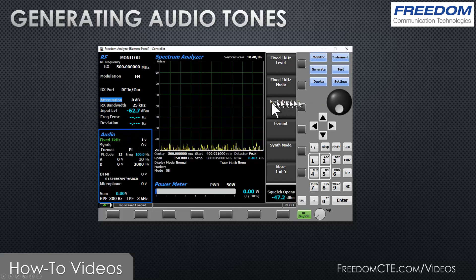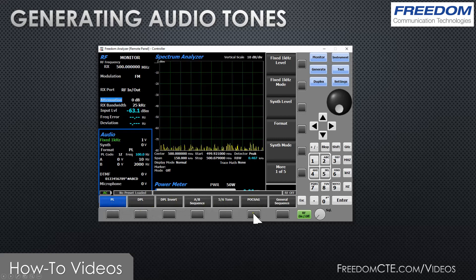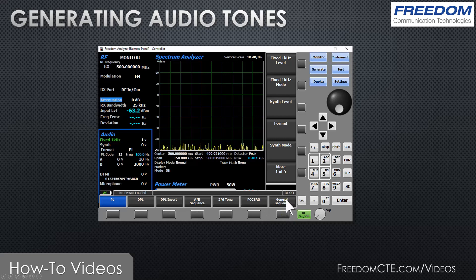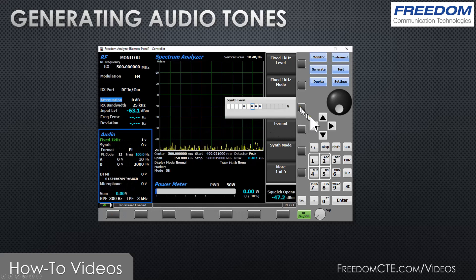I can generate not only fixed one kilohertz tones — we have a general purpose synthesizer whose format is controlled here. I can send out PL or CTCSS, DPL or DCS, DPL invert, AB sequence, or two-tone, five/six-tone, POCSAG paging tones, or I can even set up a general sequence of tones where I can specify the tone frequency, the tone duration, and the duration of the delay between tones. In this case I'm going to select PL. I'm going to leave the PL code as 1Z. I have to give it a level, so the synth level I'm going to set to one volt.